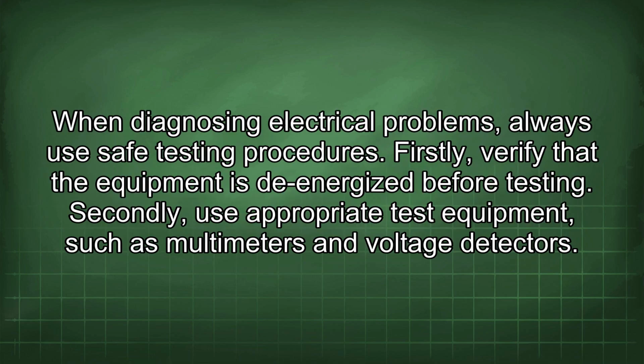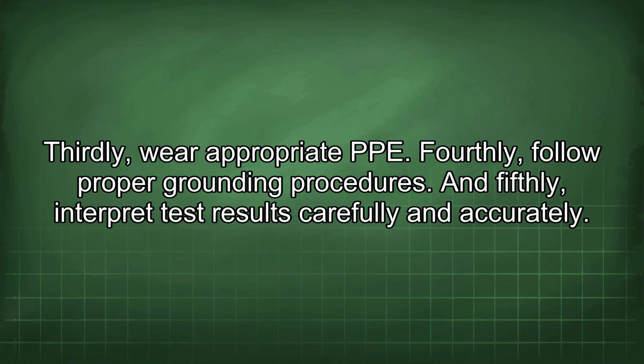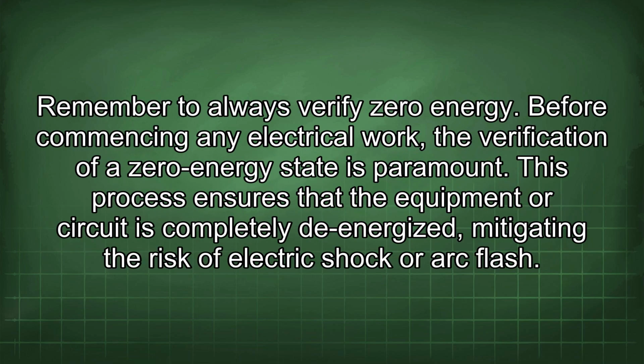When diagnosing electrical problems, always use safe testing procedures. Firstly, verify that the equipment is de-energized before testing. Secondly, use appropriate test equipment, such as multimeters and voltage detectors. Thirdly, wear appropriate PPE. Fourthly, follow proper grounding procedures. And fifthly, interpret test results carefully and accurately. Remember to always verify zero energy.